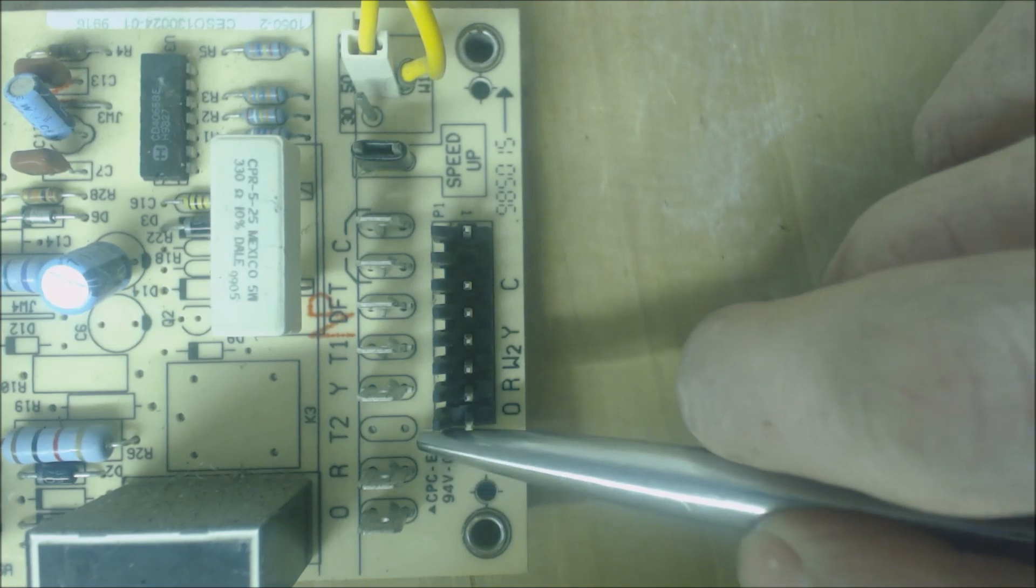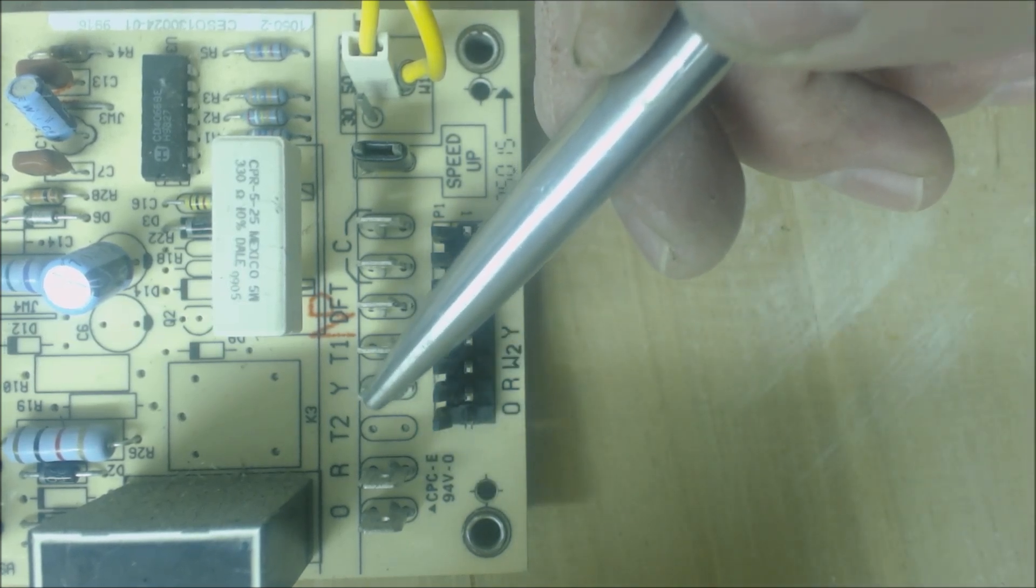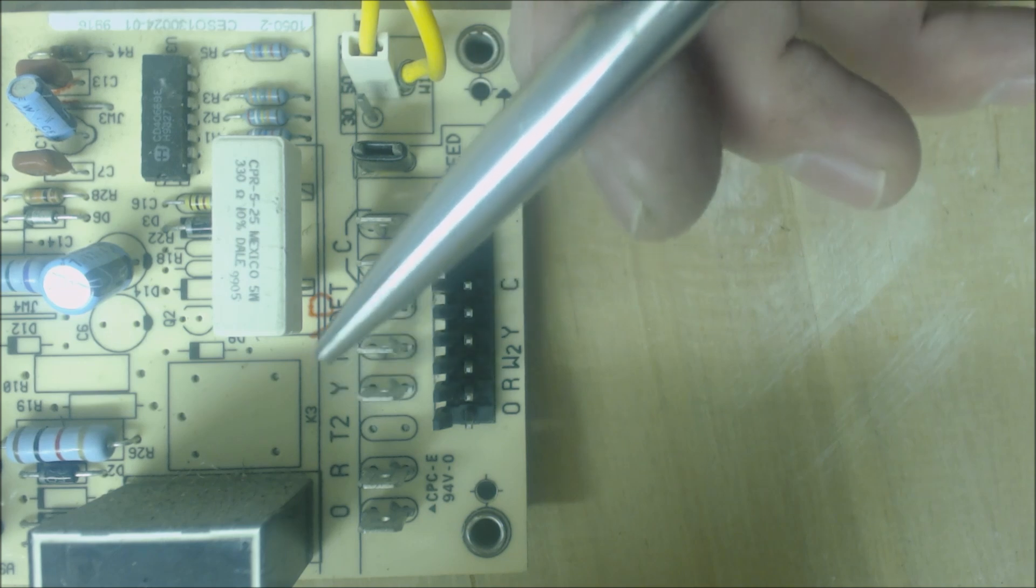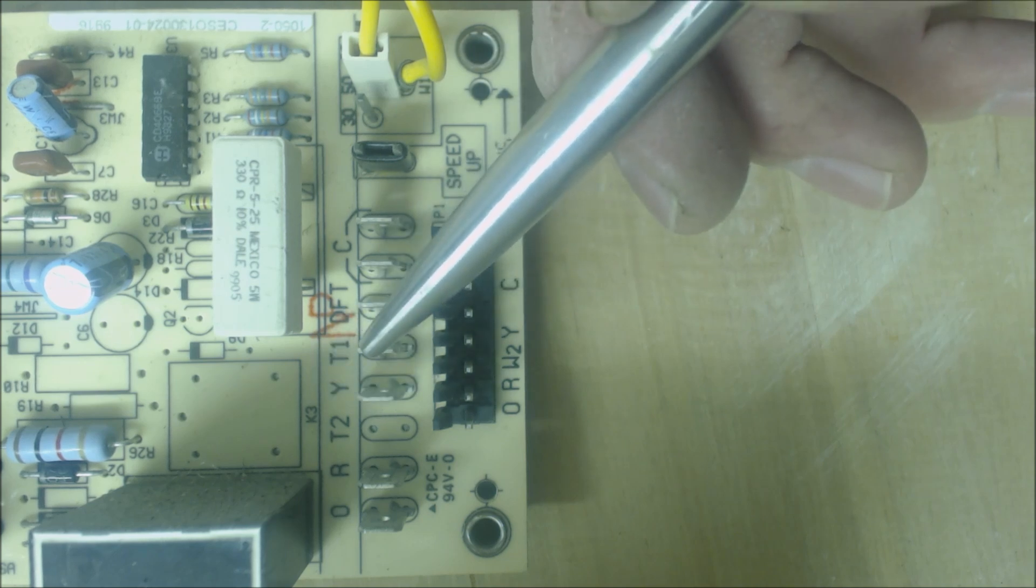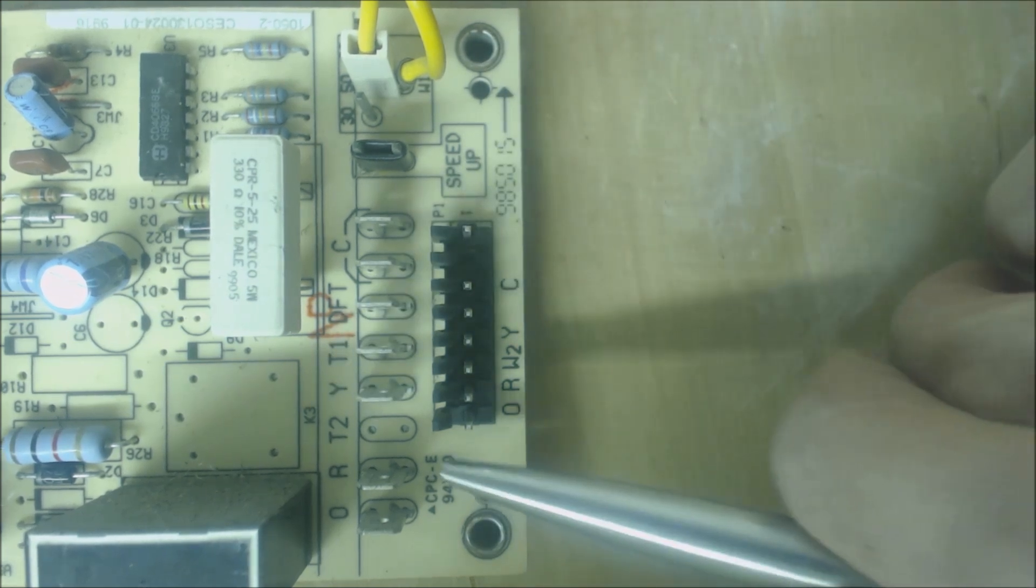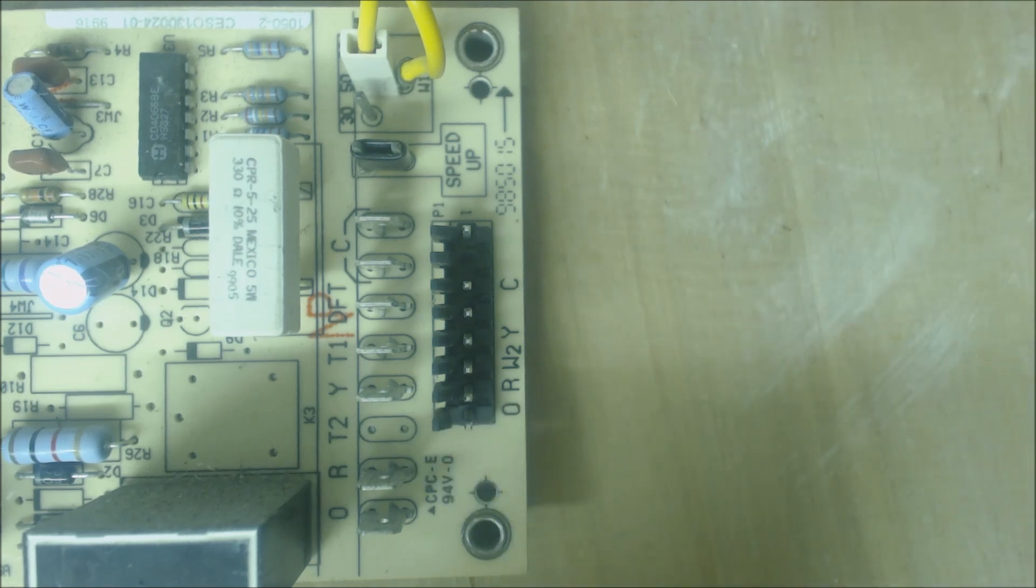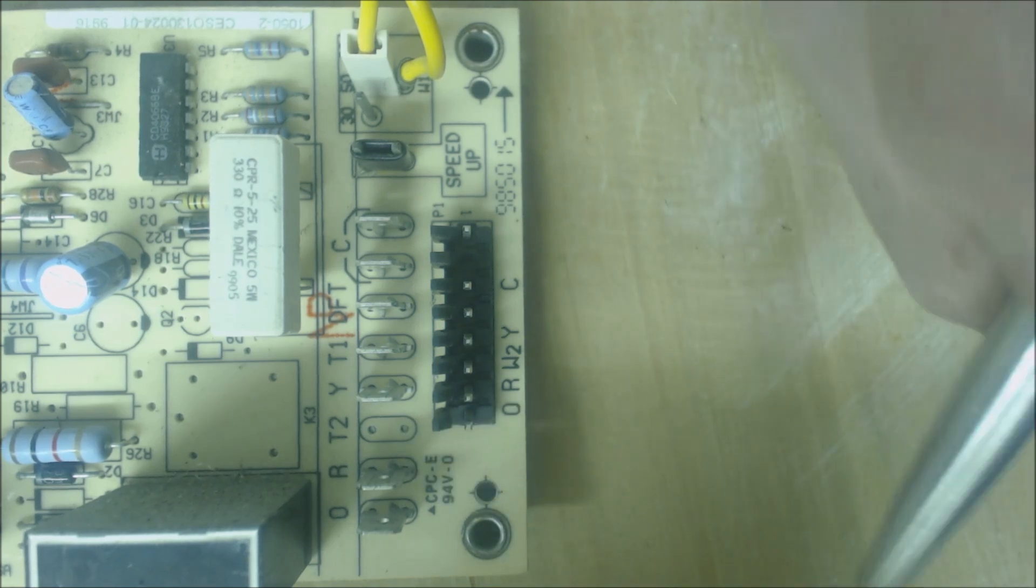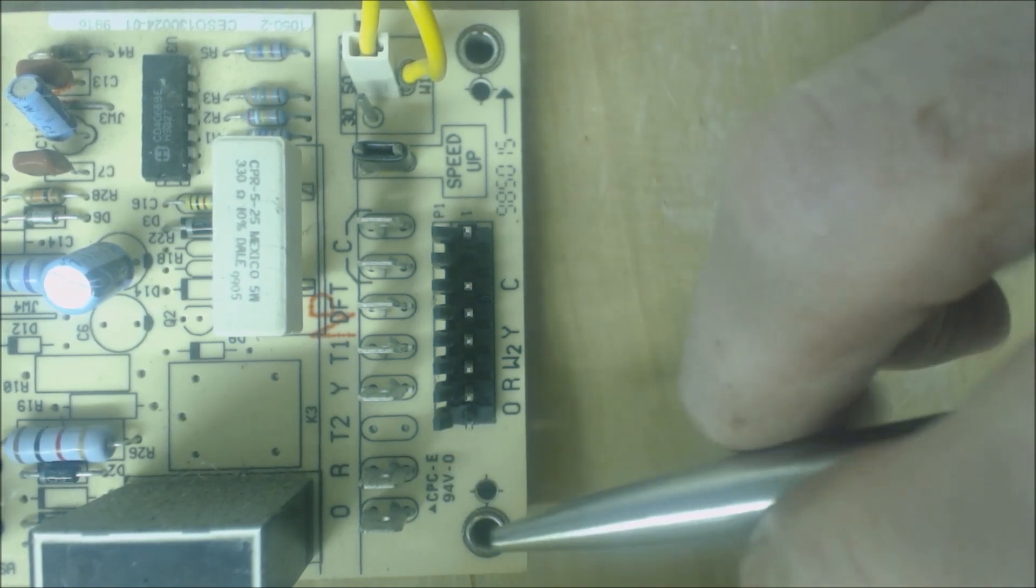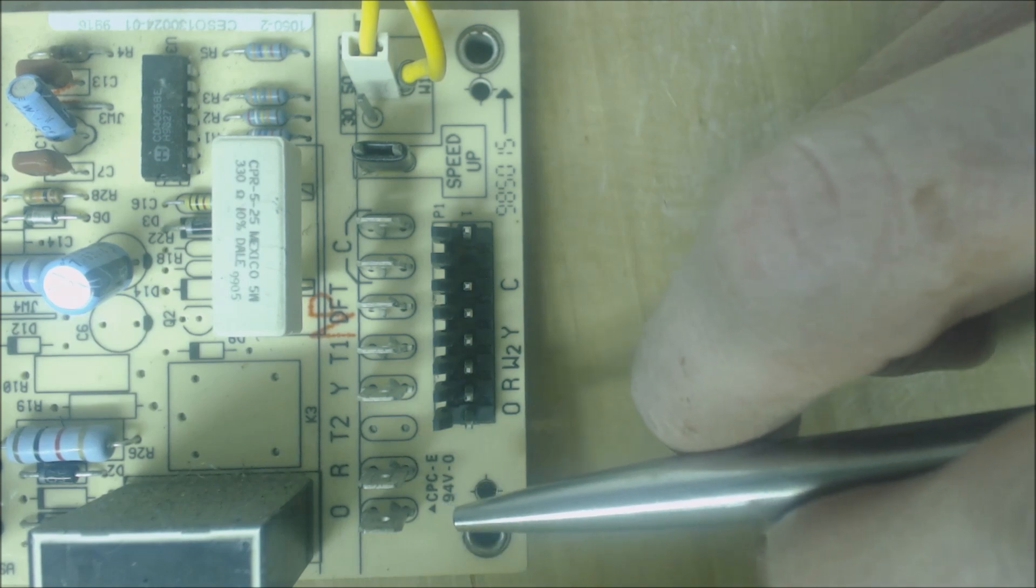If T2 is here, it will go from Y through the pressure temperature sensors to T1, and then the board would send 24 volts off from T2 to the contactor. That's why I wanted to go over this, just to make sure you guys were aware of that.